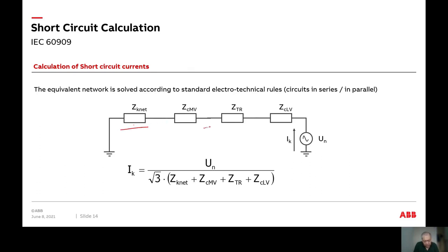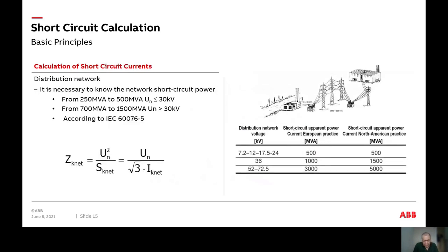We have converted the medium voltage cable, transformer, and LV cable to their equivalent impedances. To find the short circuit current after the LV cable, we use Ohm's law: current equals the secondary voltage divided by root three (three-phase system) and the sum of all impedances. This is very simple — not rocket science. For the distribution network, we can find the impedance based on the network voltage and rated current, or based on power if the current is unknown.